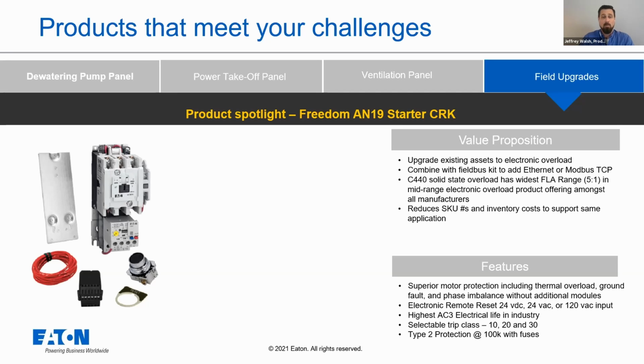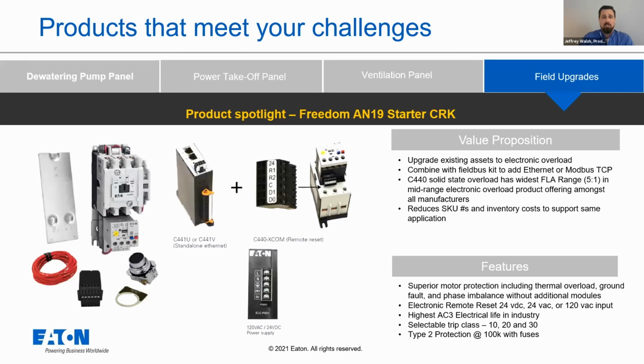The competitive retrofit comes with, as you can see in the image, a backplate which is pre-drilled to match both legacy Eaton starter hole patterns as well as competitors. The kit also includes a reset push button so that there are no issues aligning the overload with any existing reset plunger. We also offer a communication kit that can be used to upgrade existing electronic overloads, so you can add it to an existing electronic overload and make it communicating, or you can combine it with the competitive retrofit kits.